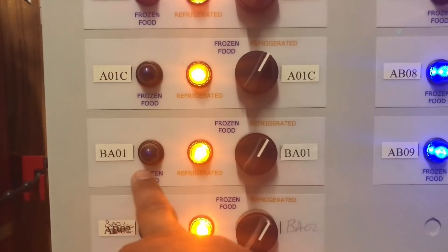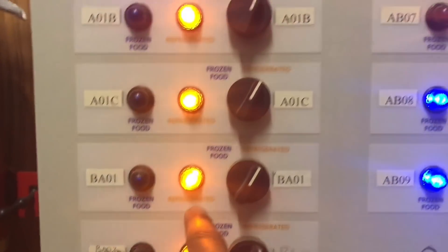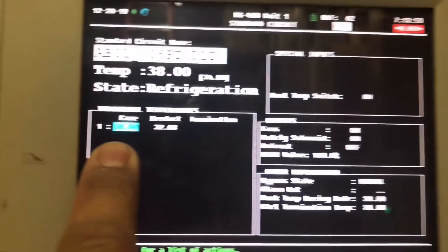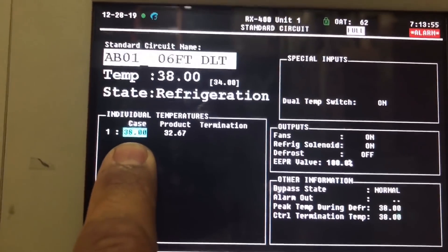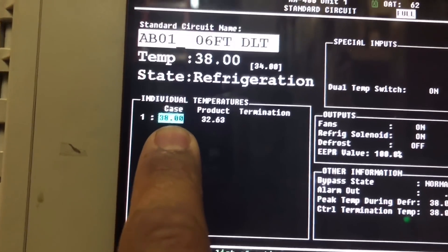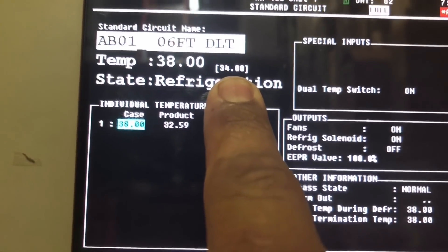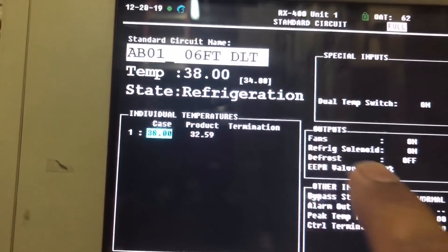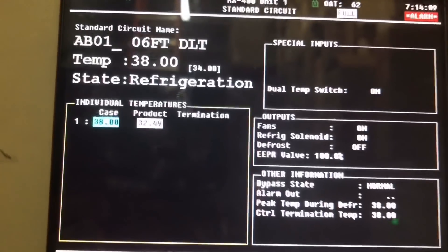AB01 right here - refrigerated, not frozen. This is why we're running so low. Whenever the monitoring company gets an alarm they generally put in an override, so they have it overridden for 38 degrees. Set point is 34, and that's why the refrigeration is calling 100% open. Let's go ahead and remove this override.